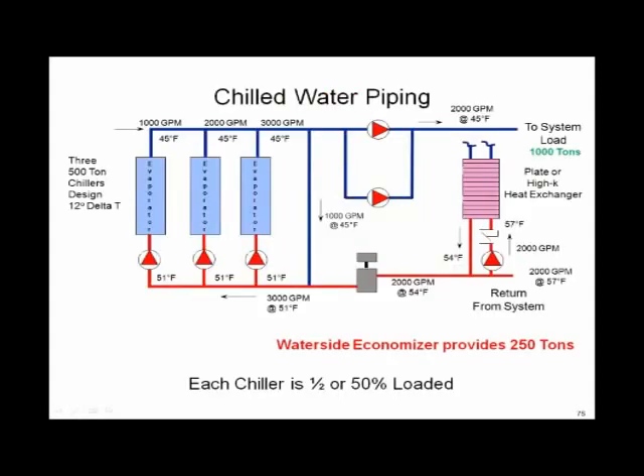The best way to show that is, this is kind of a busy slide, but take a few minutes. It's pretty basic, pretty simple. Trying to get this concept across to you, what's happening with the water side economizer when it's integrated in series with the chiller plant. Take a quick look. I've got three 500-ton chillers here. I'm using 12 degree delta T on the chiller, which means return temperature at full load would be 57. At full load, the supply would be 45, 12 degree delta T, 2 GPM per ton. Very good design, a lot of people using it. A 500-ton chiller would need 1,000 GPM. Two chillers would be 2,000, three would be 3,000 GPM of 45-degree water available.